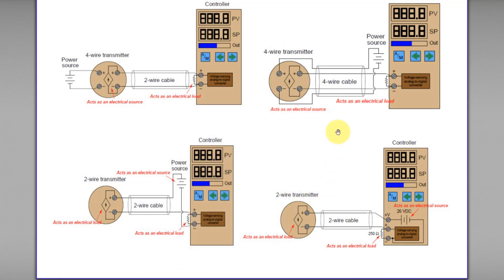How is this achieved? Very simple — you can use a calculator. Voltage equals current times resistance. Resistance is fixed at 250 ohms. If the minimum current signal in the loop is 4 milliampere, then 4 milliampere times 250 ohms gives you 1 volt. If the current is 20 milliampere, you get 5 volt. So, that's all. Peace.